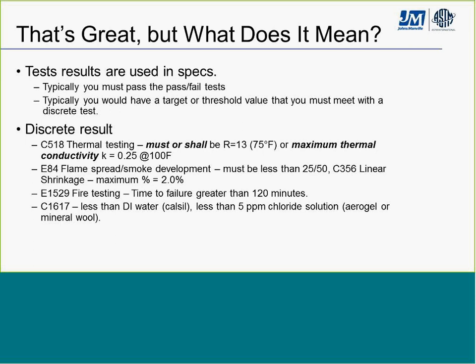Looking at maximum thermal conductivity, remember that small numbers are good and big numbers are generally not as good. But for something like sound absorption, high numbers are better than low. For ASTM E84, if it must be less than 25/50, that's usually spelled out. Linear shrinkage maximum 2%, and so on — there's always going to be some kind of interpretation in a specification. Results establish minimum product requirements, and the goal of a producer is to meet or exceed those requirements every single time.